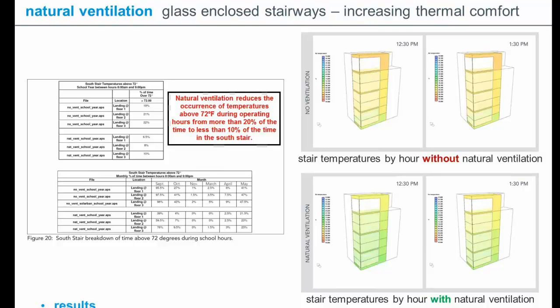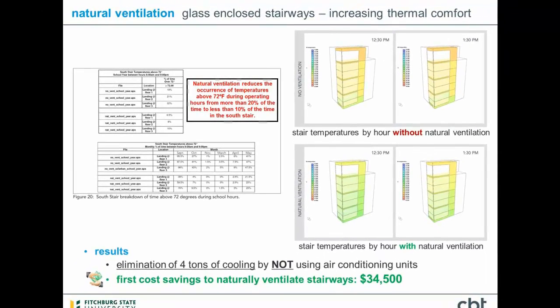And we were able to determine that just by naturally ventilating the stair, we would cut the amount of time that the stair ever went above 72 degrees in half, so that less than 10% of the time the stair would go above 72 degrees. Had we decided to address this problem with artificial cooling, which we probably would have had to because the stair was getting up into the high 90 degrees, we would have had to buy additional capacity in our cooling system to the tune of about $34,000.